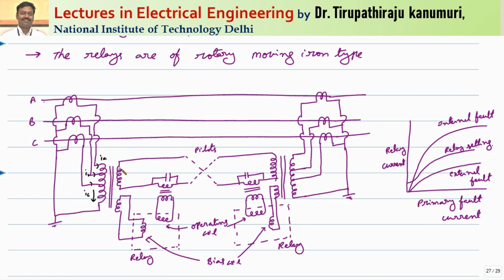Getting this one? Now under normal operating conditions, let us look at the operating coil. Let us assume that because of these currents, the current produced in this coil is like this. Similarly, whatever current is passing here for through faults, the same current will pass here, agree with me? Because of this, the current induced in the secondary, since it is connected here, will be like this. Let us assume the induced current is like this. Accordingly it will be opposite here, or otherwise this will return back like this, so we can say these two currents are in opposite directions.